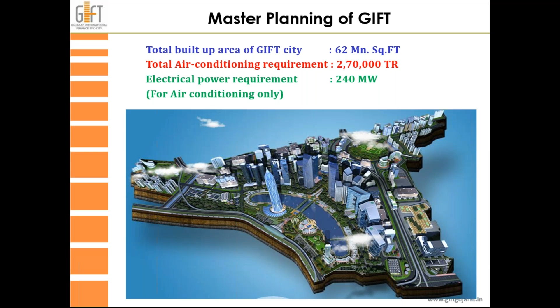Being such a city, it has residentials, commercials, social hubs, malls, and other varieties of use. If I go for a district cooling system, what will be the impact? For the requirement of 270,000 tons on the low side for building users, I just need a plant installation of 180,000 tons only, because I get a bigger diversity due to the central plant for the entire city. My power requirement comes down straightaway from 240 megawatts to 150 megawatts — almost a 35% saving in power requirement.